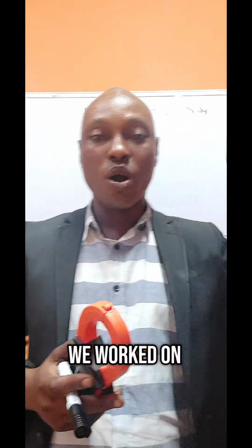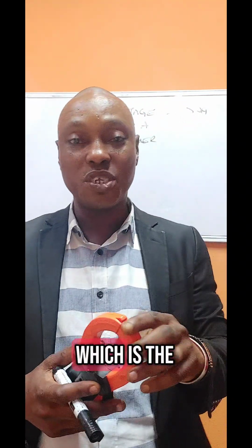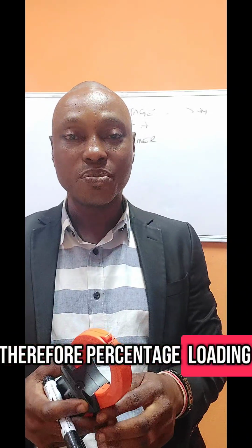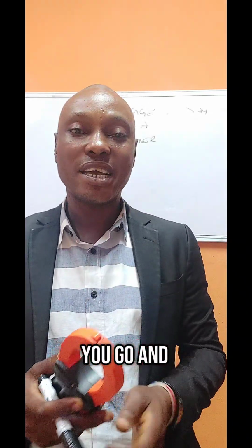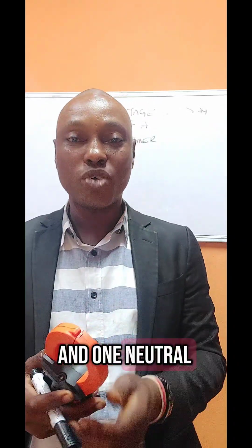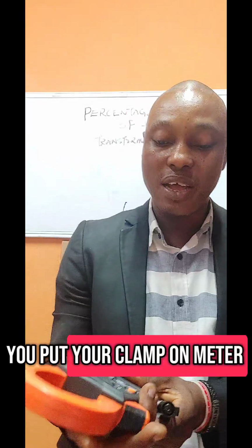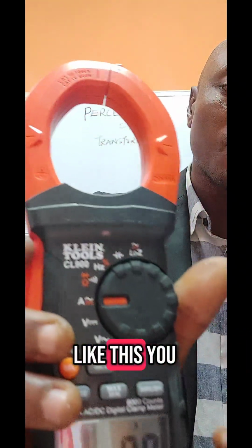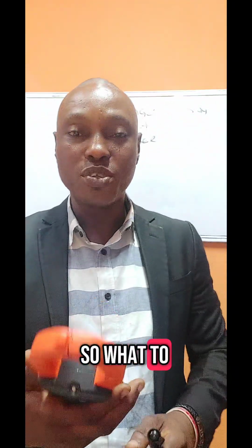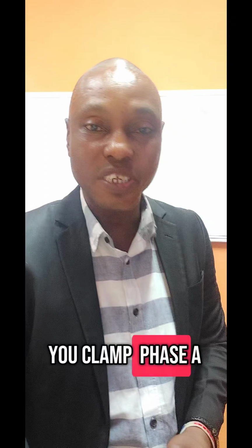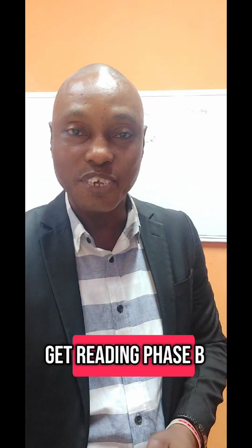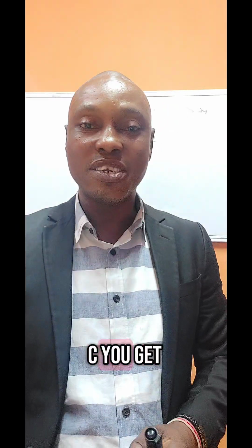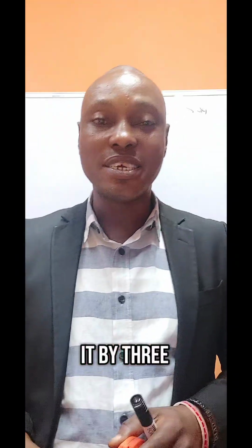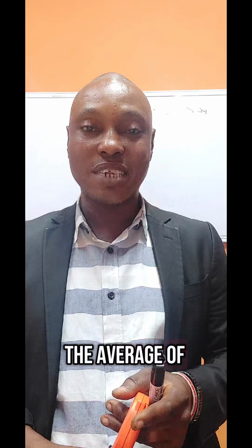When we're calculating our fuse rating, we work on the primary side, which is the line side. But for percentage loading, which is the load side, you go and check. We have 3 phase and 1 neutral. You put your clamp meter on the amperage setting like this. Once you put it on the amperage, you clamp phase A, you get the reading. Phase B, you get the reading. Phase C, you get the reading. Then you add the 3 together and divide by 3. That is the average reading of that transformer.